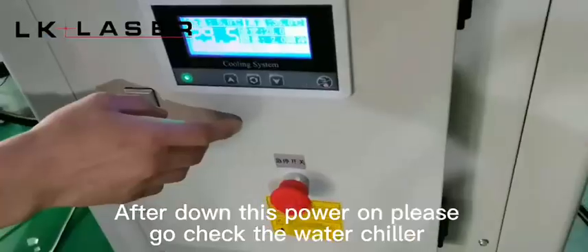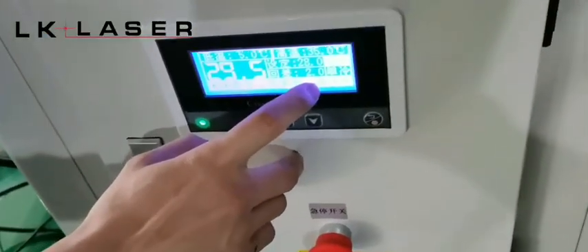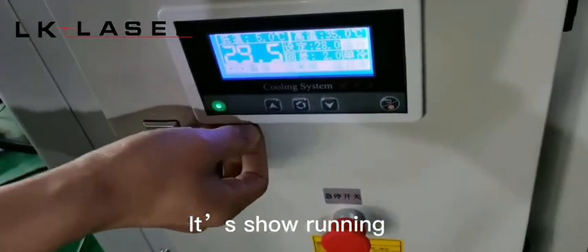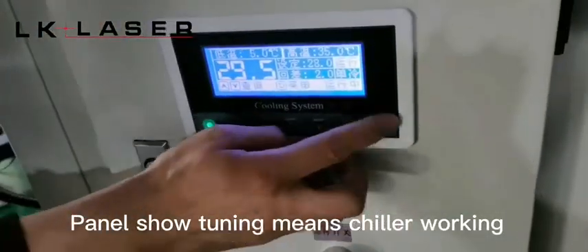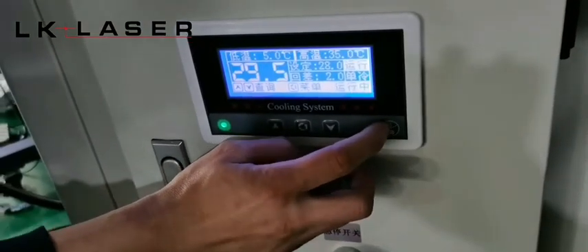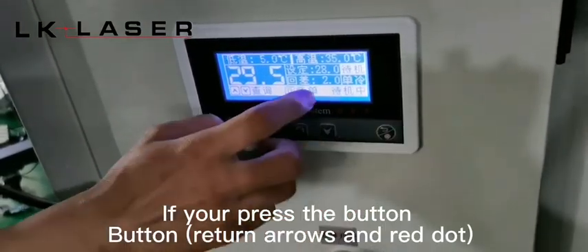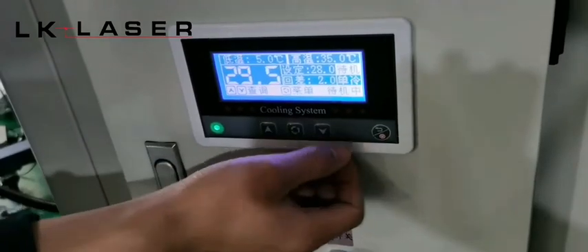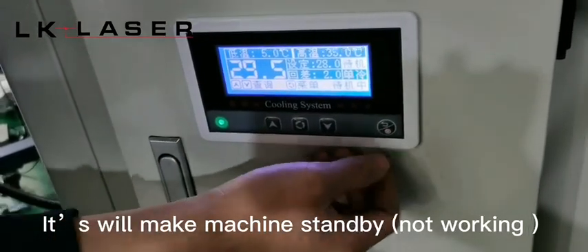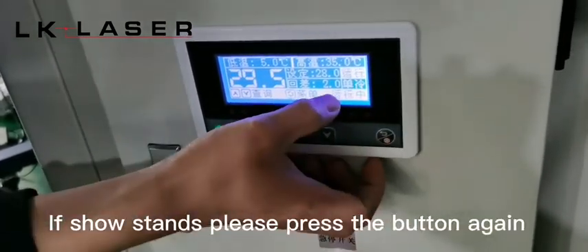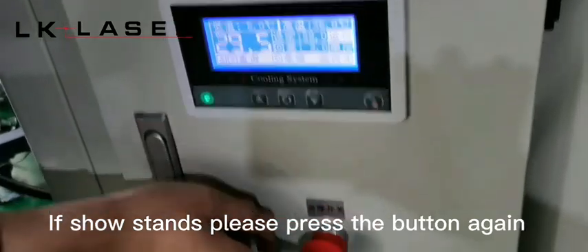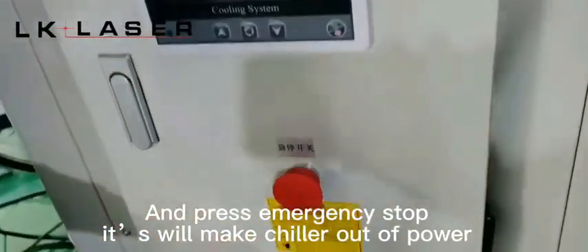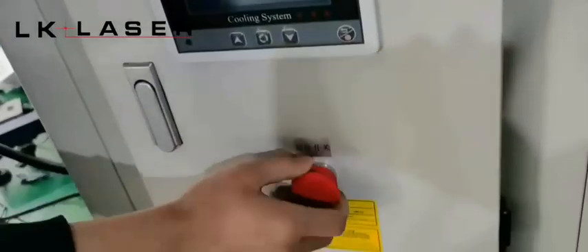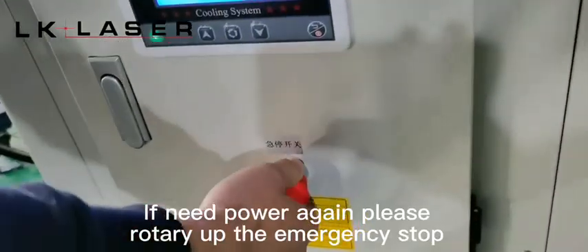After doing this power on, please go check the water chiller. It shows running. The panel showing running means the chiller is working. If you press the button with return arrows and red dot, it will make the machine standby, not working. If it shows standby, please press the button again. And pressing the emergency stop will make the chiller lose power. If you need power again, please rotate the emergency stop up.